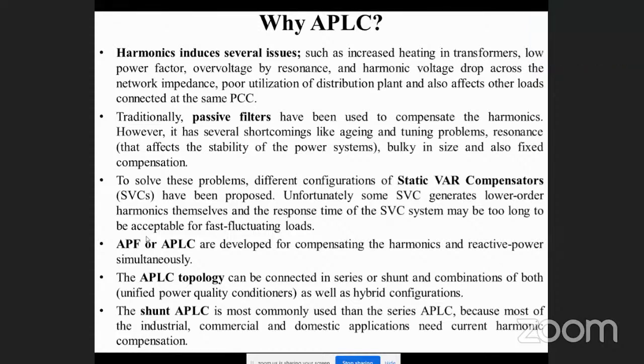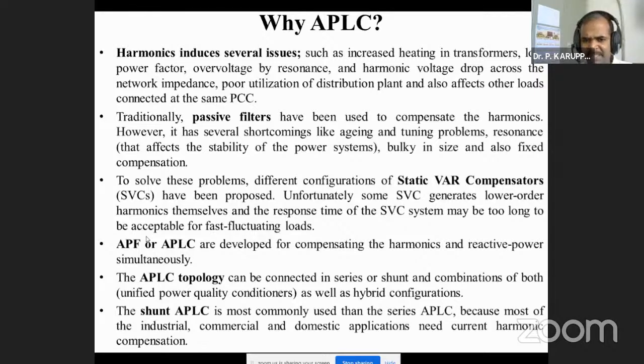Traditionally, passive filters have been used to compensate the harmonics. However, they have several shortcomings, like aging and tuning problems. So every 5 years you need to change the passive filter because of the aging problem, and the resonance may affect the stability of the power system. They are also bulky in size and give fixed compensation. Suppose I need to fix one filter separately for the third order harmonic and a separate filter for the fifth order harmonic. To overcome all these problems, different configurations like the static var compensator have been proposed. Unfortunately, some static var compensators generate low order harmonics themselves, and the response time of the SVC may be too long to be acceptable for fast fluctuating loads. So when the load is fluctuating, the response time of the static var compensator is very poor.